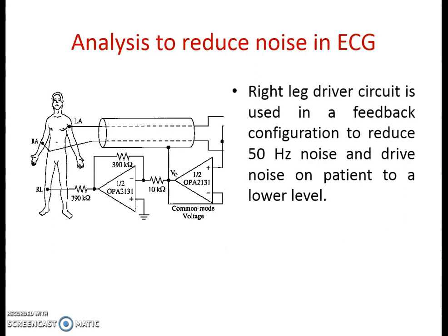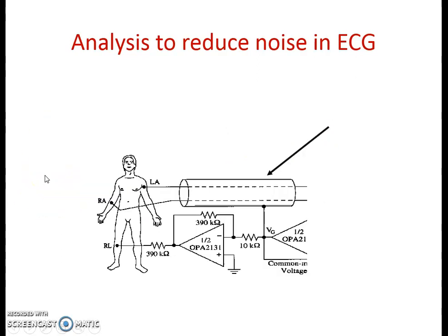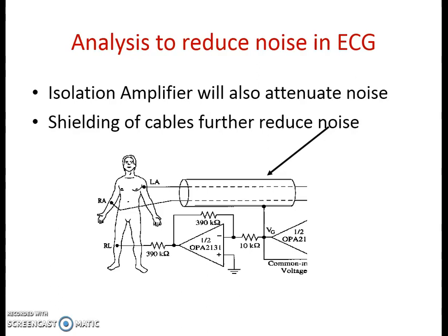The second way to deal with common mode signal is by using a right leg driver. In this circuit, part of the signal is inverted — the common mode voltage first goes to a follower and then to an inverter. Part of the signal is taken back through the follower stage and through the inverter sent back to the patient. By this particular arrangement, we are providing feedback to the patient so that the noise level at the patient can be reduced. Using the isolation amplifier will also help reduce the noise level. In addition, shielding of cables also helps to reduce the noise further.